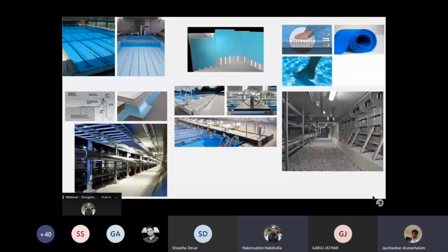On my bottom right, you will see what a corridor looks like, and on my left, the 2 extremes, you will see examples of a corridor solution that our technology allows. This means that all the electromechanical elements of the pool are easily accessible for maintenance. Every electromechanical element, all the piping, all the cabling, everything will be immediately behind our panels and accessible to the maintenance staff.